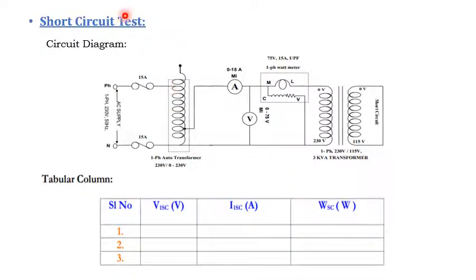Next, the short circuit test. Now this is the circuit diagram of the short circuit test. In this test, just observe the transformer which is under test. Here the LV side is short circuited with a thick conductor, and the HV side is given supply through some meters, that is wattmeter, ammeter, and voltmeter, in order to measure the short circuit current, short circuit voltage, and the short circuit power, or it is also called the copper loss.